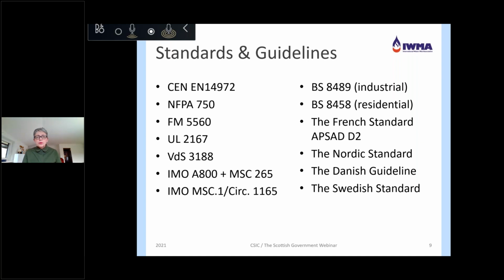But most of the standards are listed here. For us, the most important standard is the EN standard. EN 14972 Part 1 was published in December 2020. That's the part entitled Design, Installation, Inspection and Maintenance. In there, the concept that water mist systems are performance-based is defined and described. The European standard reflects the uniqueness of each system.